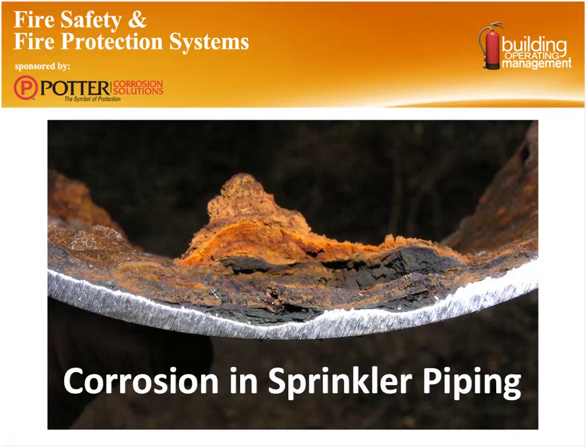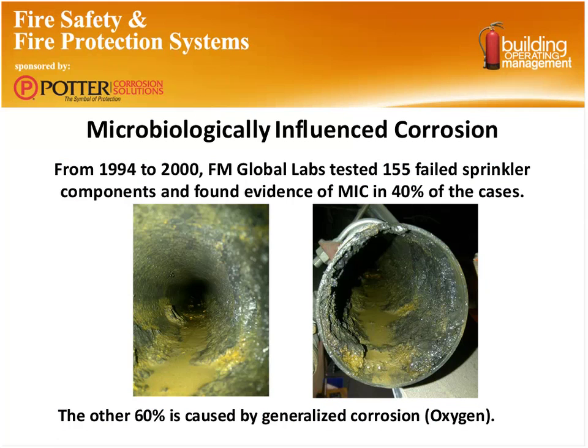Corrosion in sprinkler piping has been a known issue for quite a few years. Initially, everybody thought most corrosion was microbes, or microbiologically influenced corrosion. Between '94 and 2000, FM tested 155 different failed sprinkler systems, and they found evidence of MIC, or the microbes eating the actual pipe, in about 40% of the cases. The other 60% were caused by general corrosion, which is due to oxygen within the water in the pipe.